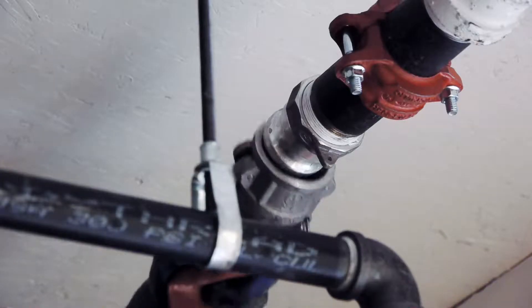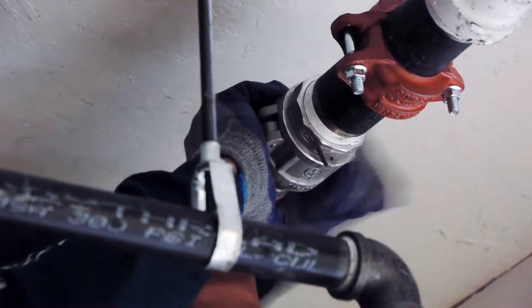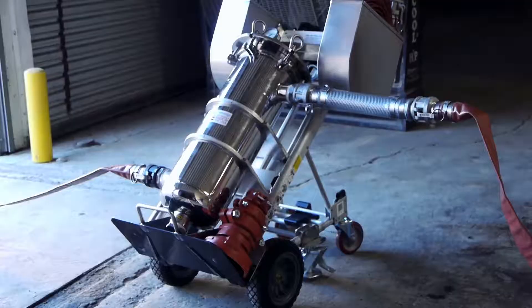Install the transition piece to the reducing coupling or fitting using the existing Victaulic coupling. Connect one female end of the flat hose to the male cam and groove fitting and the other end to the sight tube. Make sure the hose is as flat as possible with no folding or kinks to restrict flow.